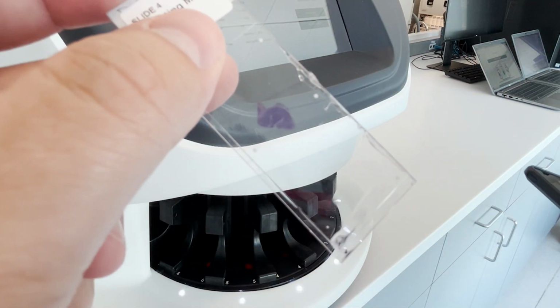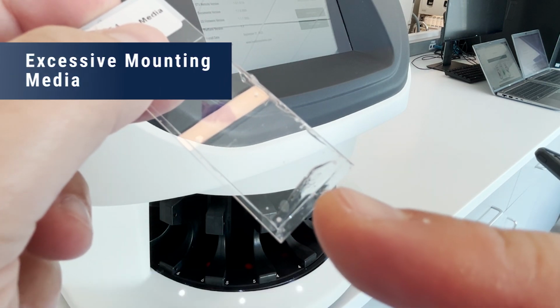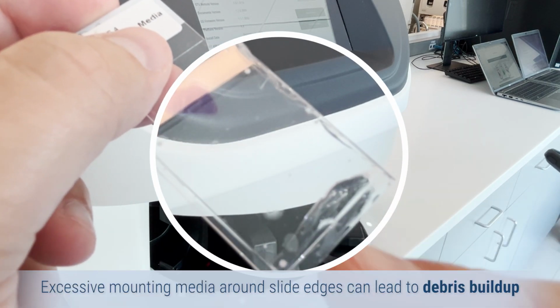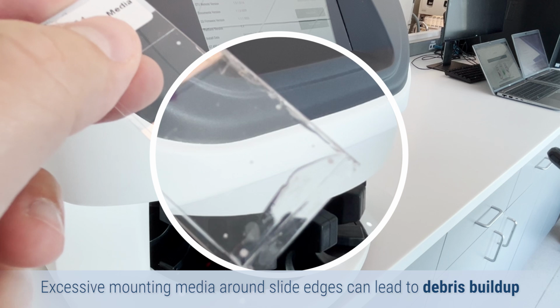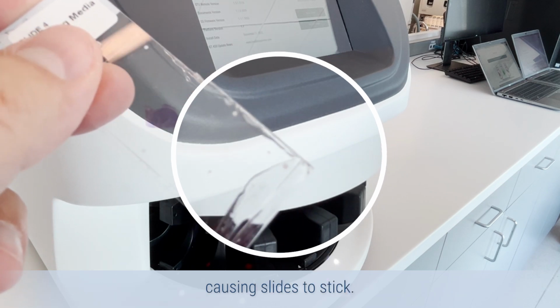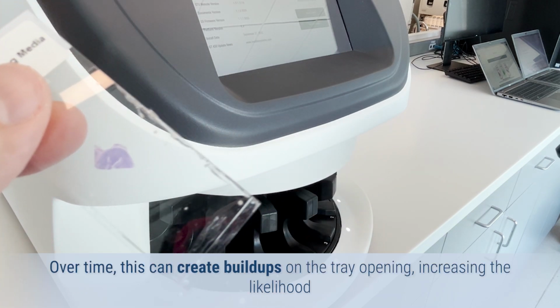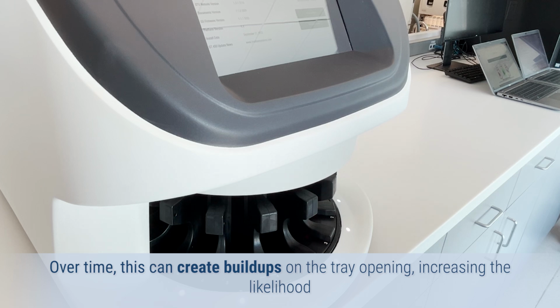Number 3, excessive mounting media. Excessive mounting media around slide edges can lead to debris buildup in the slide rack slots, causing slides to stick. Over time, this can create buildup on the tray opening, increasing the likelihood of handling errors.